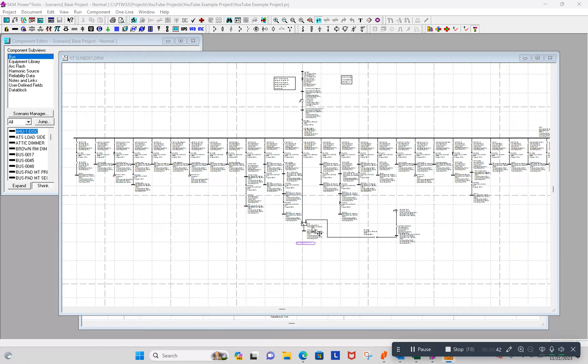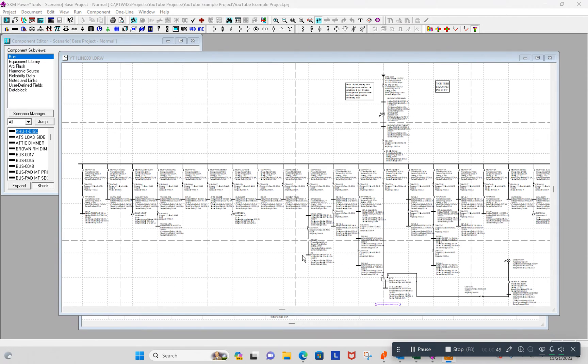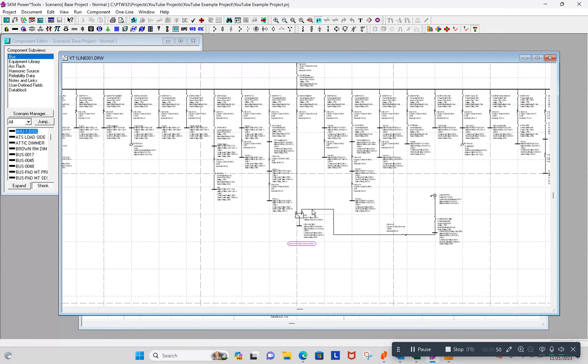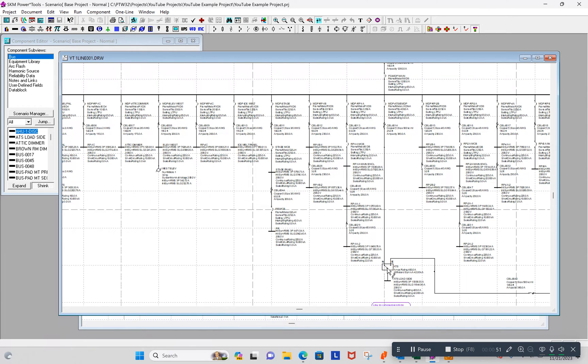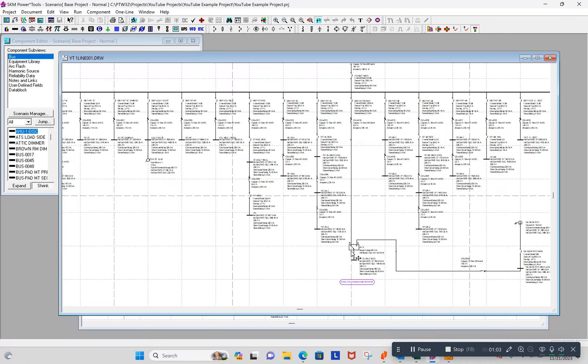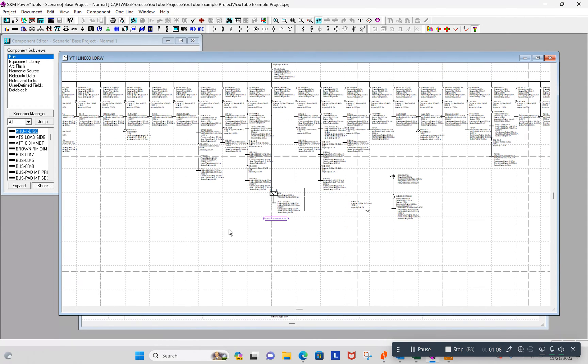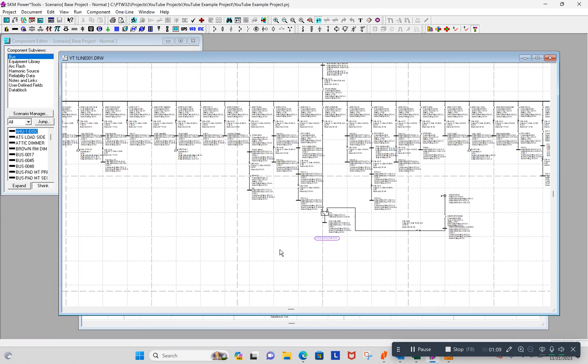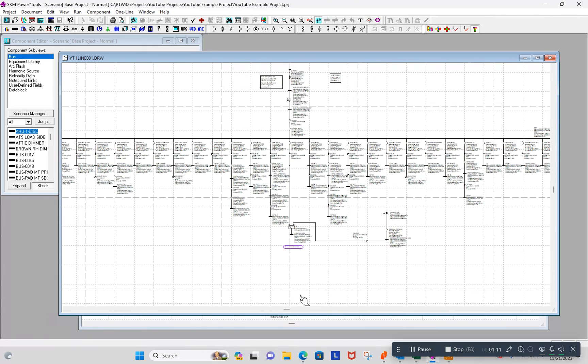Or maybe you want to do a different scenario with the load, emergency loads on the generator or not. Right now you can see that the transfer switch is in the normal position. So if I run this study, all it's going to do is calculate the downstream of this transfer switch fault currents and arc flash incident energy based upon the transfer switch being in the normal position.